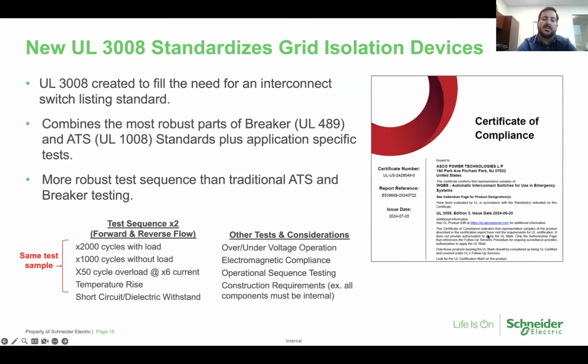Well, if we need these products to be labeled, what exactly do we label them to? Historically, there were no standards around this, actually. But most recently, UL has worked on an outline of investigation, which is basically a standard for all intents and purposes. It's the preliminary steps to a full standard called UL 3008, which is specific to interconnect switching. And it's the first standard around this space. And it's for critical applications and emergency applications, similar to the way you would see a UL 1008 for a transfer switch. The similar naming between 1008 and 3008 is intentional because they are very similar standards for a very similar application. So the naming is meant to be together.